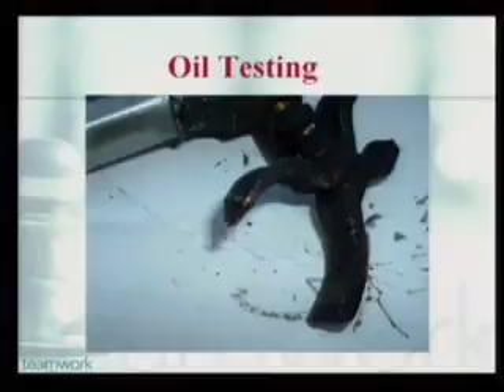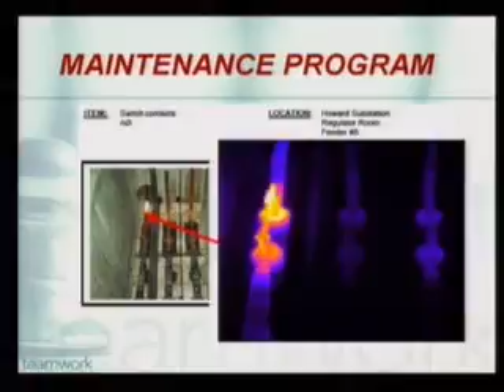The other non-intrusive testing that we do is the infrared testing on our devices. This is basically taking an infrared camera and taking pictures of connections to see what they look like with respect to the environment as well as the system right next to it. In this particular example, this is a bus connection in Howard Substation, where if you look closely on that face that's overheating, that component, compared to the other two faces, is lighting up bright. And what that tells us is this program we use to locate what we consider hot spots. We look for loose connections, and the whole goal of this is to do corrective measures, make corrections before they fail. As you know, in previous outages, we would report that something failed, overheated.